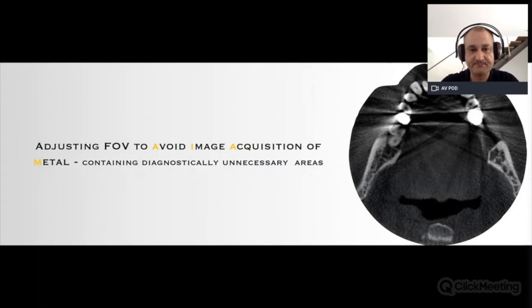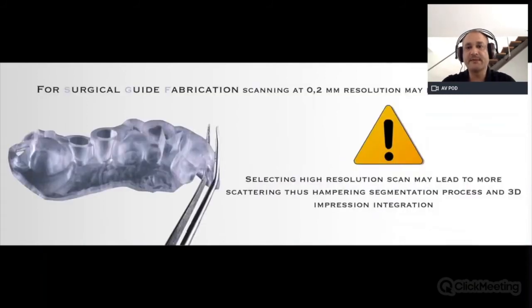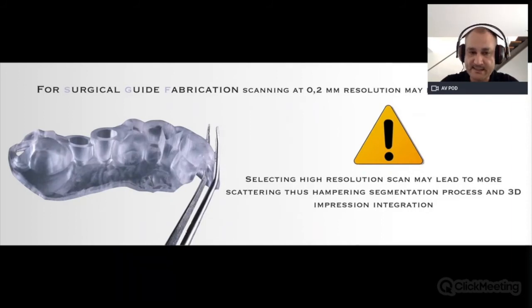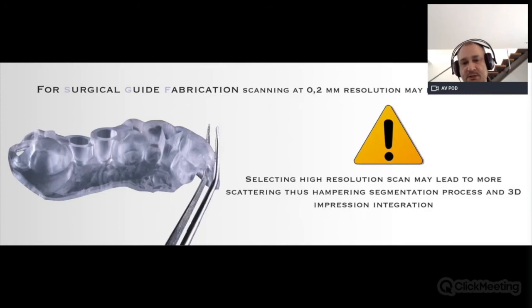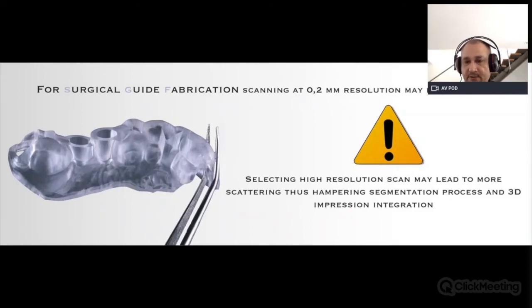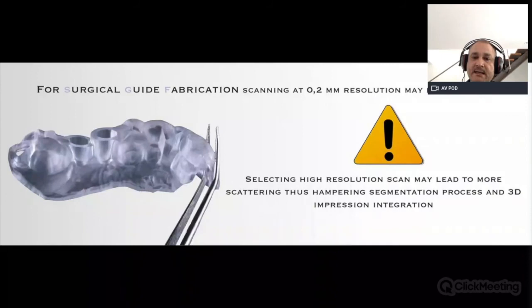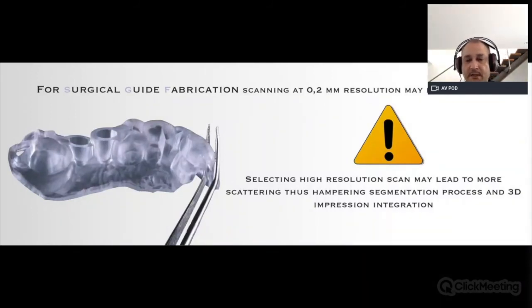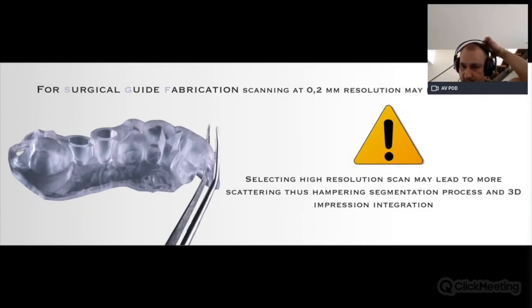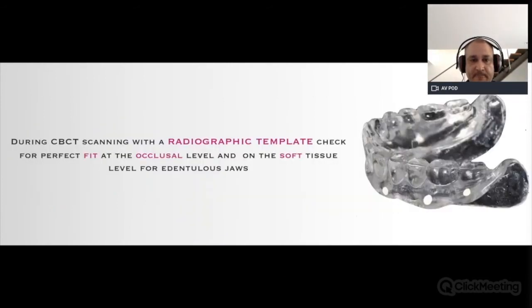Knowing that the sufficient resolution for a nice surgical guide is only 200 microns, we should adjust our resolution accordingly — not too high. We should use the minimum resolution needed to acquire our image, whether 200 or 300 microns, to minimize scattering and acquisition time. This will help us have a cleaner image and enable nicer segmentation and better integration of our 3D cast.